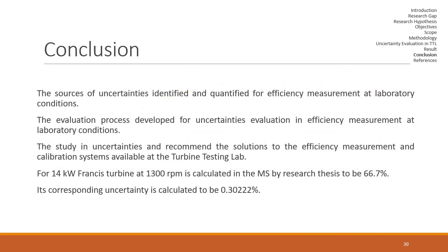Evaluation of uncertainty in measurement system is very essential for every test. Since Turbine Testing Lab was initiated with the sole motive to test different turbines, standardization in calibration was necessary. The research worked on identification of sources of uncertainties and quantification for the measurement systems at laboratory conditions. It also worked in development of the evaluation process of uncertainties and verification of measurement system at laboratory conditions as per IEC standards. The research was only limited to calibration of torque transducer for shaft torque measurement due to lack of equipment and resources.